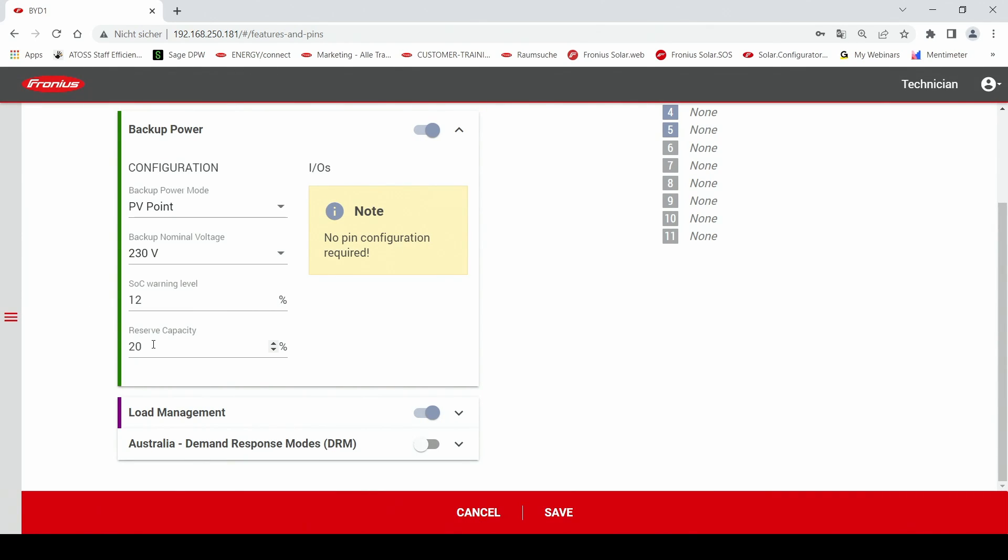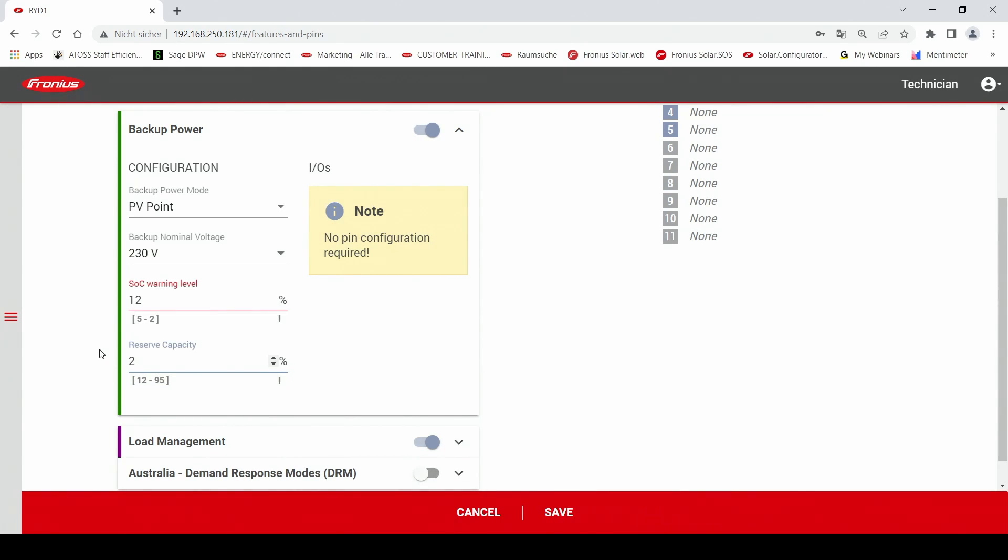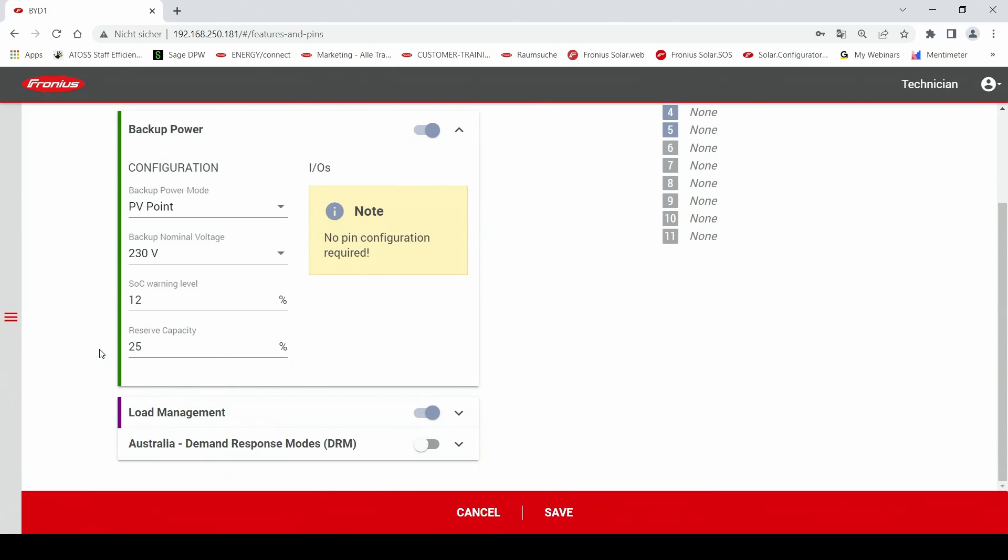Second on you can also set the reserve capacity and with that you can make sure that amount of the battery storage for example 25% is always reserved for the backup power. So with that you can make sure that even during cold winter nights when the public grid fails that you have your backup power solution available.